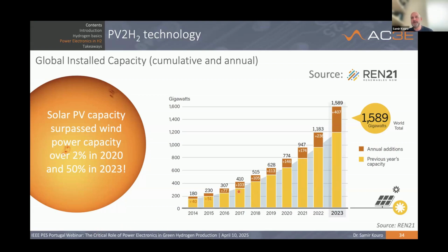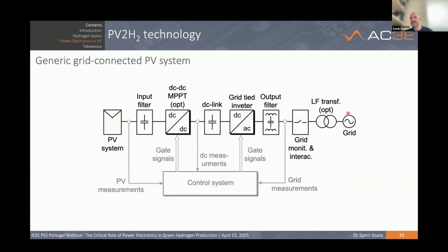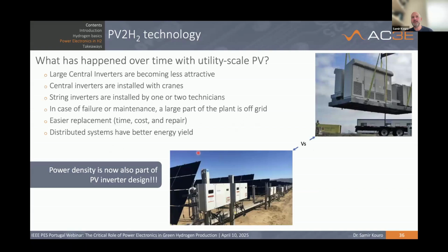We've experienced huge growth in photovoltaic energy, I guess in Portugal as well. This is the typical PV system connected to the grid, two stages. Initially most PV systems used this kind of converter, very large scale grid-tied inverters. You need a truck and a crane to bring this to your PV plant and put it in place. Whenever one of these fails, you can lose up to 1 or even 3 megawatts, since today's large-scale inverters go up to 3 megawatts.